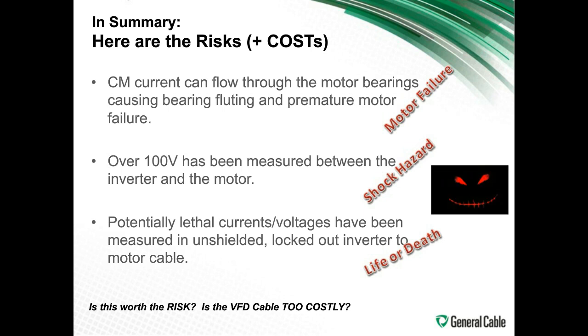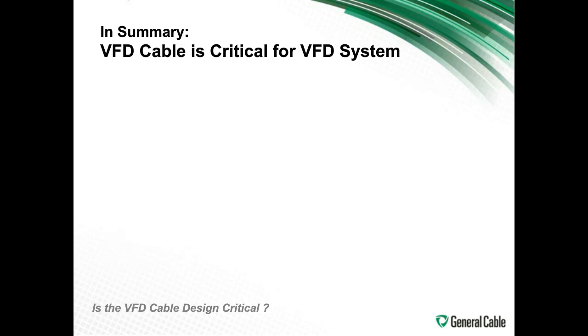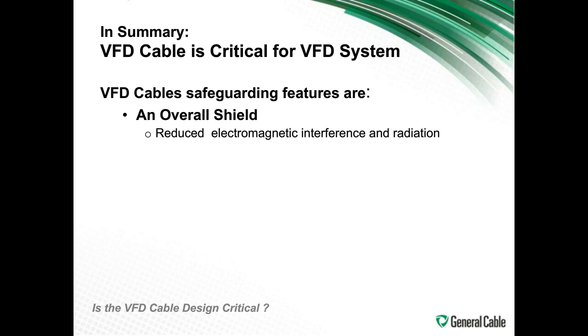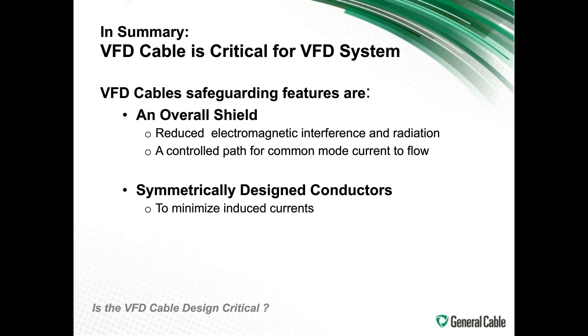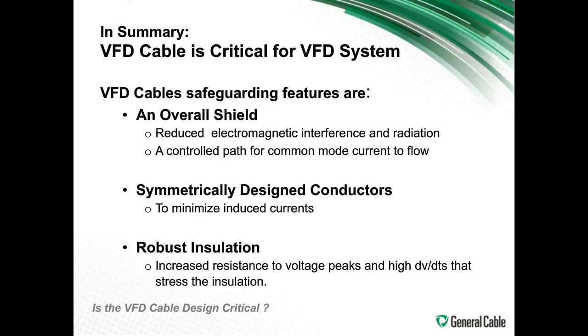So that is what we have to think about, that evil that is created from the VFD drive. What can we do about that? We have to look at investing in a good motor cable. So in summary, the VFD cable is critical to the VFD system. VFD cables' safeguarding features are an overall shield to reduce electromagnetic interference and radiation, a controlled path for the common mode current to flow, symmetrically designed conductors, that way you would minimize induced currents, and robust insulation. That way you increase the resistance to voltage peaks and high dV/dTs that stress the insulation, and they will not cause problems with the cable itself and wear out the cable in the process.